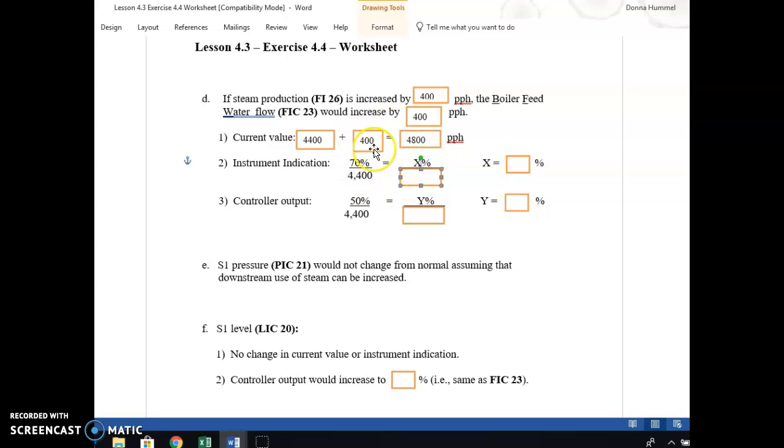What's our instrument indicating? So we go back to our normal operating conditions table at 70%. At 4,400, it's 70%. And here our ratio at our new number is 4,800. What is the percentage rating? This is just teaching you ratios. It's all mathematical. It's linear. That is equal to 76.4. We're going to put it in like that. Then the output, because FIC23 is a controller, at 4,400 it's normally open 50%. So what is the new output from the valve going to be? At our new number of 4,800, that will equal 54.5. Let's put that in there.